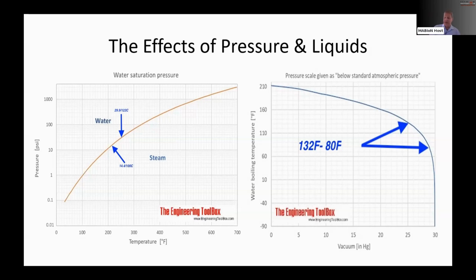On the other side of the chart, this is your vacuum. At atmospheric pressure, the boiling point is 212. But then you start pulling a vacuum. When the autoclave goes into vacuum, most autoclaves should be able to pull between 25 and 29 inches of vacuum. At 30 inches of vacuum, you're at the vacuum of space. But you can see the numbers here.